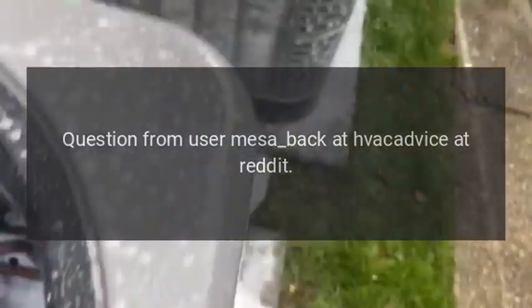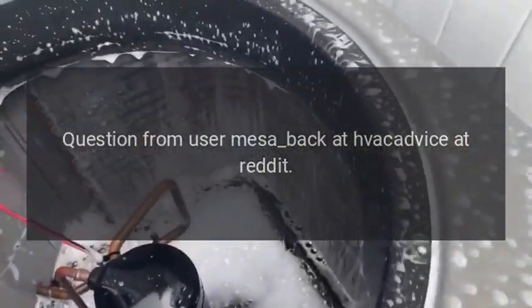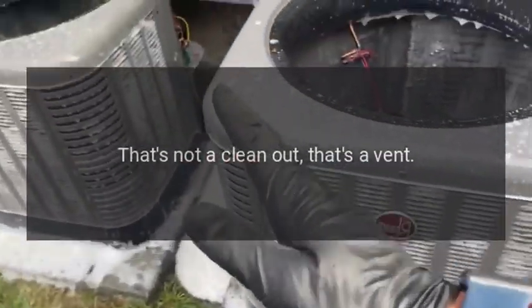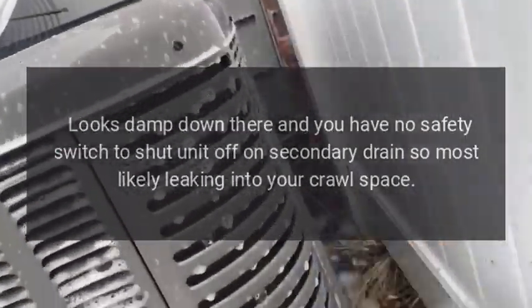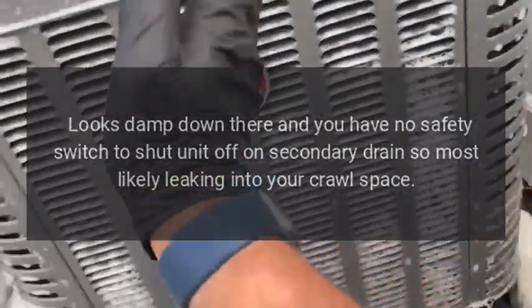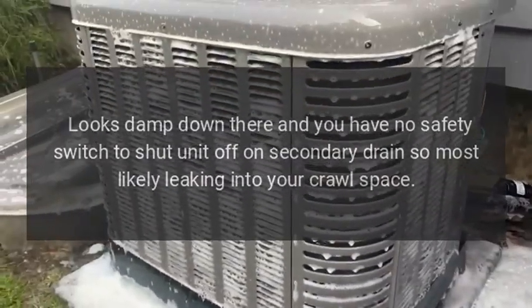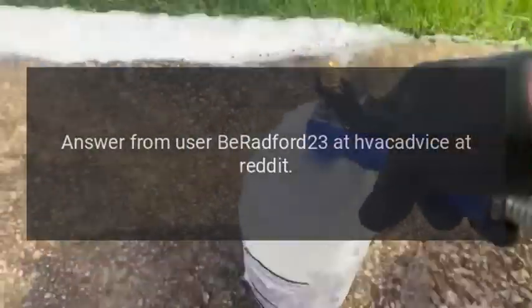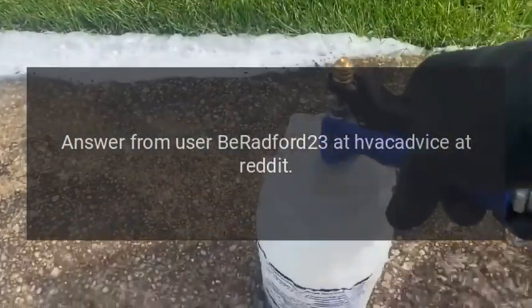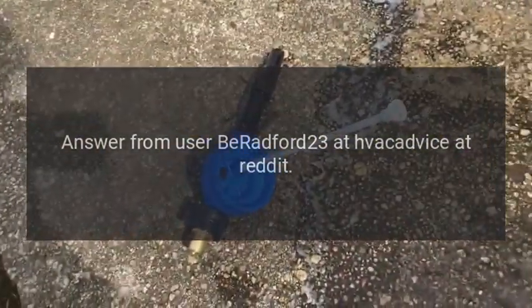Question from user mesa_back at HVAC Advice on Reddit. Answer: That's not a clean-out, that's a vent — it just might need cleaning out. It looks damp down there and you have no safety switch to shut the unit off on a secondary drain, so it's most likely leaking into your crawl space. Answer from user BeRadford23 at HVAC Advice on Reddit.